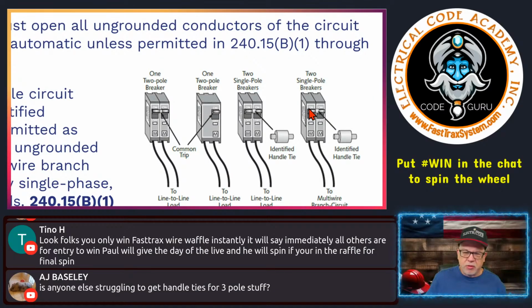Because if there's 20 amps on this one and 20 amps on this one, then it's going to see 0. But conceivably, you could be pulling 0 on this one and the maximum of 20 amps on this one. The maximum imbalanced load that this neutral could see in a multi-wire branch circuit is 20 amps. It couldn't see any more than that. And if this one all of a sudden comes on, then the neutral is actually going to go down if you install it properly. And that's why you have it set up this way.